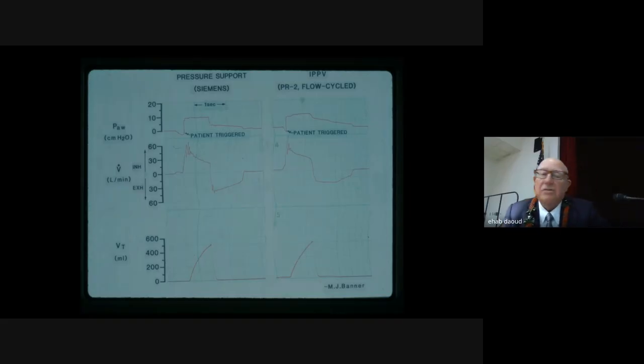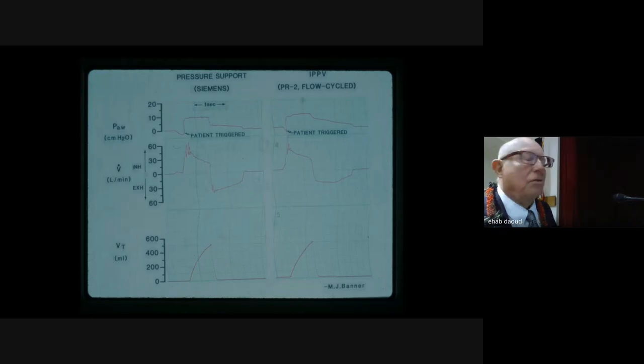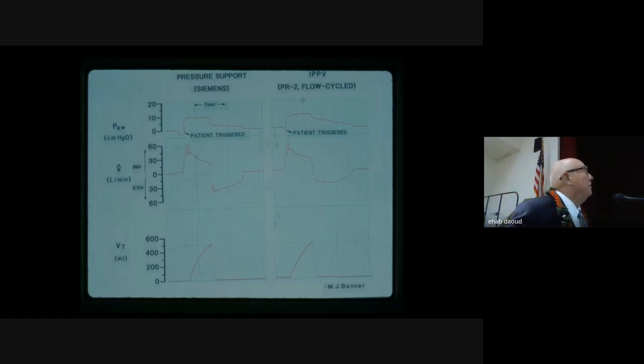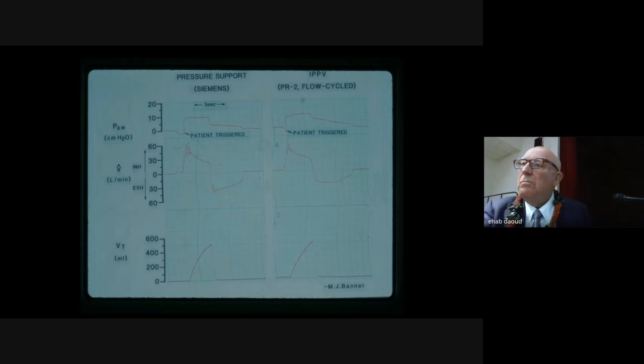One of our ex-colleagues, Mike Banner, gave me this slide some years ago. On the left-hand side, you see the Puritan Bennett PR2. I'm sorry, on the right-hand side, the Bennett PR2 flow-cycled ventilator that is triggered on by a patient inspiratory effort. You can see below the flow, and you can see that the flow terminates at approximately 75% of the inspiratory flow, and then the tidal volume below is 500 milliliters. On the left-hand side is the Siemens with pressure support. In other words, they're identical. Pressure support is just flow-cycled mechanical ventilation.